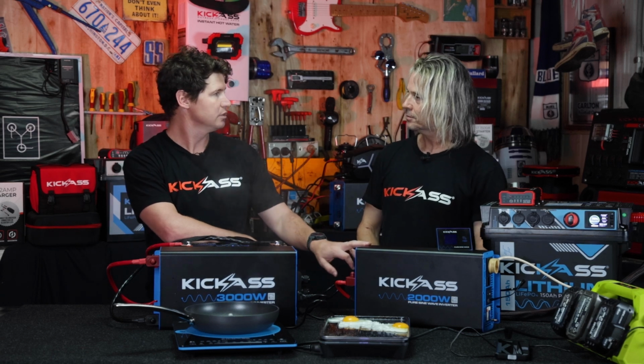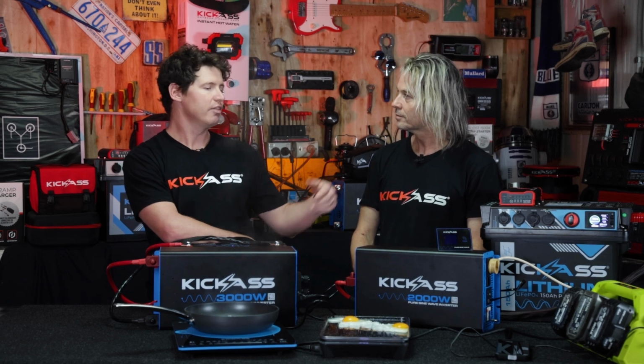And what would happen if you overload these? Yeah, so with overload, the first protection will be software protection. If it detects we're going over the 2000 watts, it will cut out, then test to see if that input has been disconnected to recover the device. If there's a short circuit or earth leakage fault, then the RCBO - that's the RCD with the circuit breaker in it, the safety switch - that would then trip.